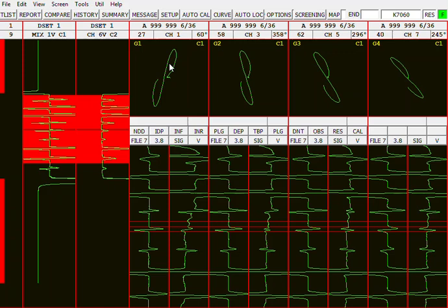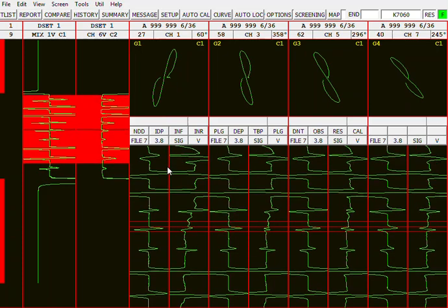It actually doesn't start until you get a ways through the tube wall. And this phase is indicative of some disturbed eddy currents. So if it's a 60% flaw from the OD, you're going through 40% of the tube wall's good material, then the rest of the tube has a flat bottom hole there. So you get some phase lag.